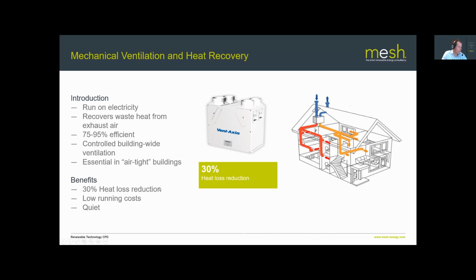Overall, because they tend to be fitted in quite well insulated, quite airtight buildings, you can see about a 30% reduction in heat losses. And as long as it's designed correctly, the running costs are very low, and they're very quiet. I was in a house with MVHR on Friday, and even standing directly under the vents, you could not hear it at all. It was super quiet.